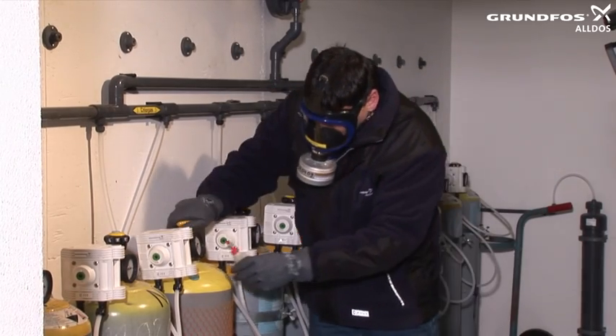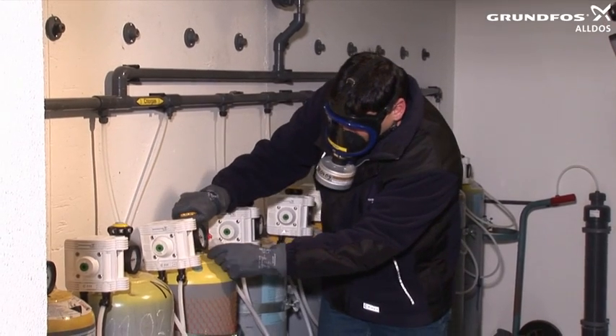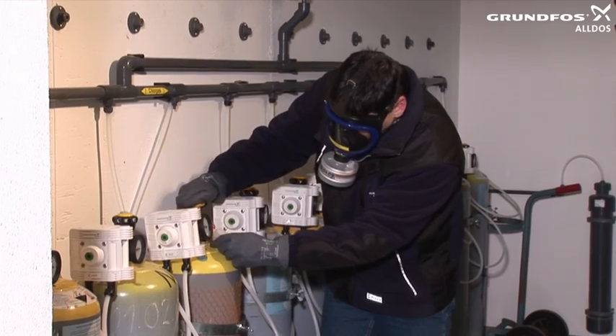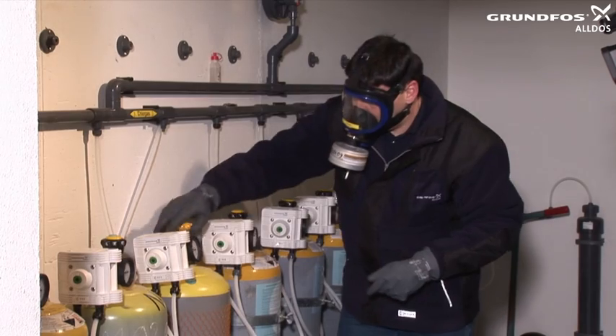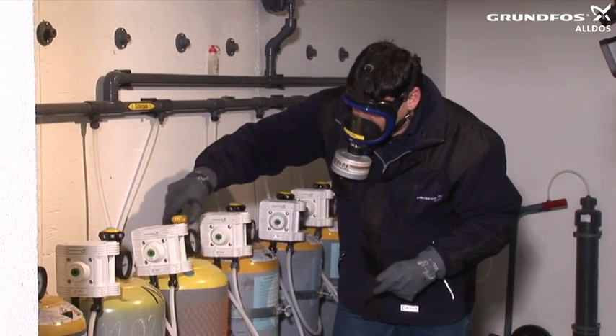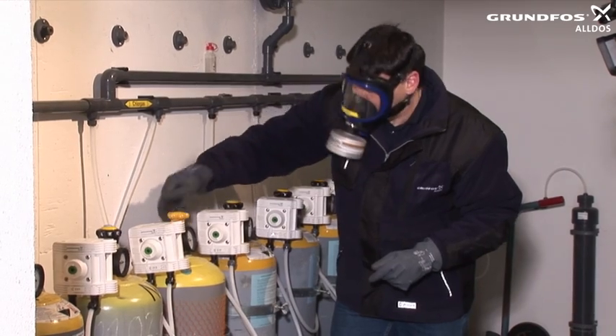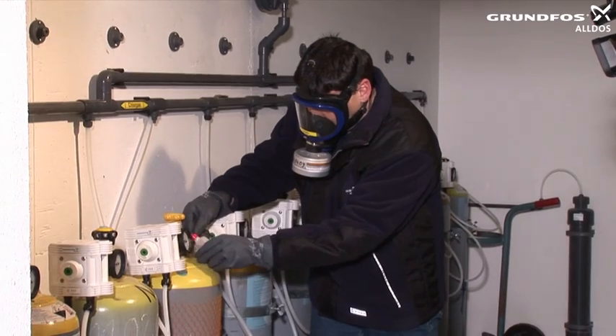Open the chlorine gas cylinder valve and close it immediately once the pressure has built. Carry out an ammonia test and check whether the pressure on the manometer drops. If there is no chlorine gas escaping, that is, if the ammonia test does not produce a cloud and the pressure has not dropped, completely open the chlorine gas cylinder valve. Tighten it back up by half a turn and check again with ammonia.